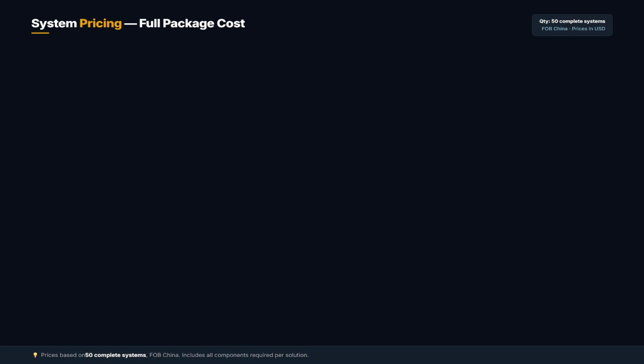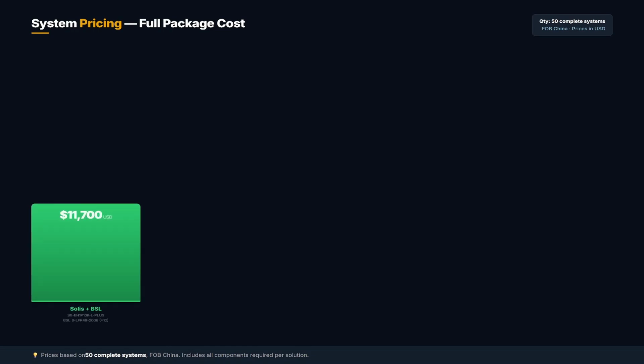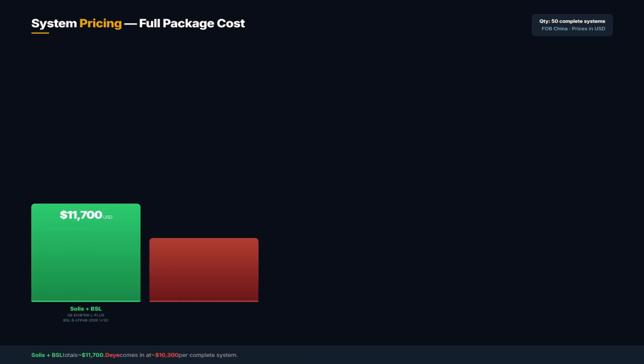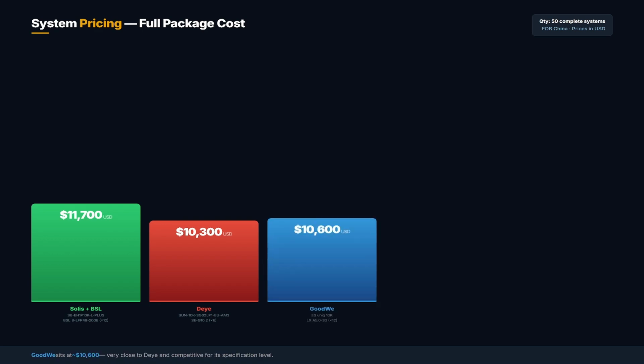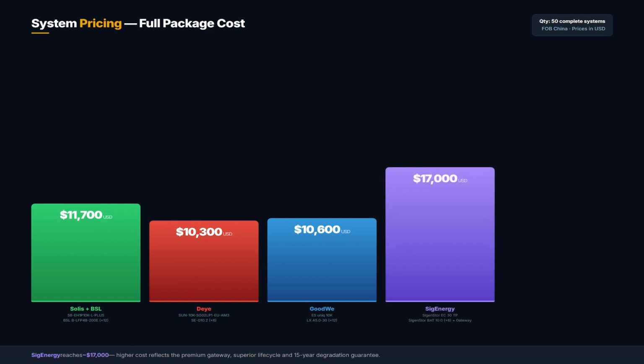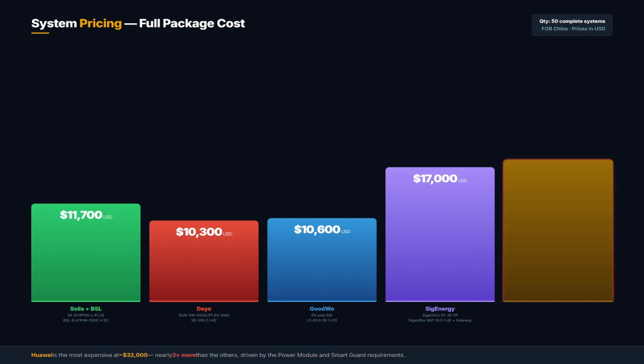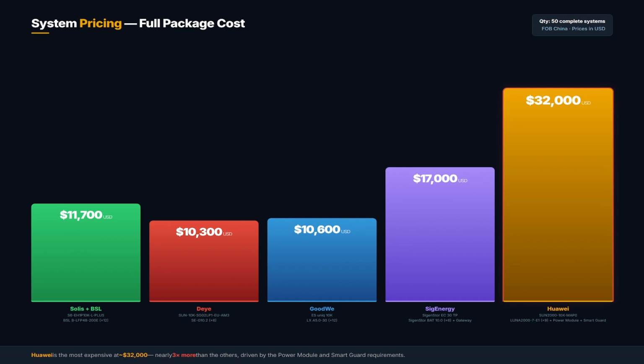Considering these configurations and unit prices, we can calculate the whole system prices. For the Solis BSL combination, the total cost is approximately 11,700. For Deye, it would be 10,300. For GoodWe, 10,600. For Huawei, it will reach approximately 32,000, which is almost 3 times that of GoodWe, Deye or Solis. And SigenErgy is about 17,000. These prices are quoted in US dollars, delivery FOB China.